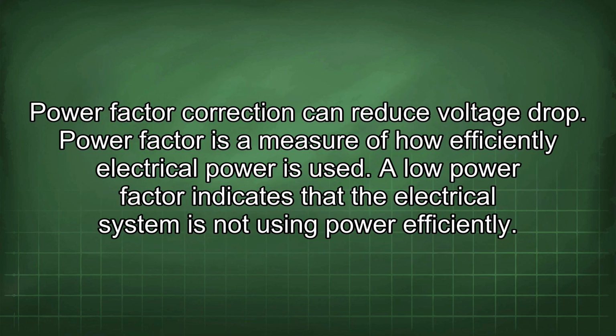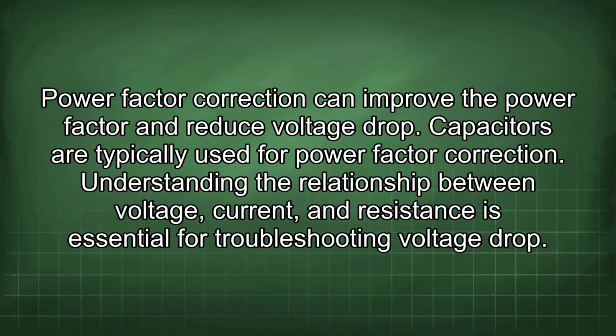Power factor correction can reduce voltage drop. Power factor is a measure of how efficiently electrical power is used. A low power factor indicates that the electrical system is not using power efficiently. Power factor correction can improve the power factor and reduce voltage drop. Capacitors are typically used for power factor correction.